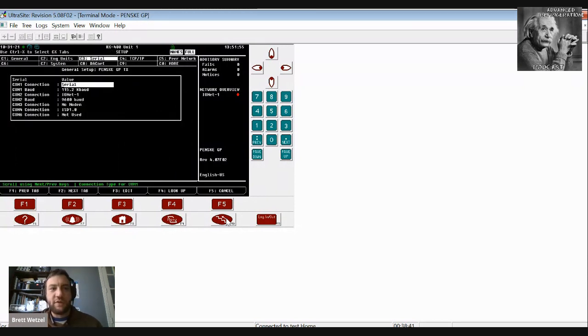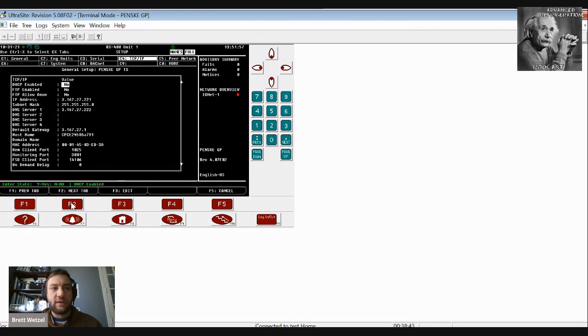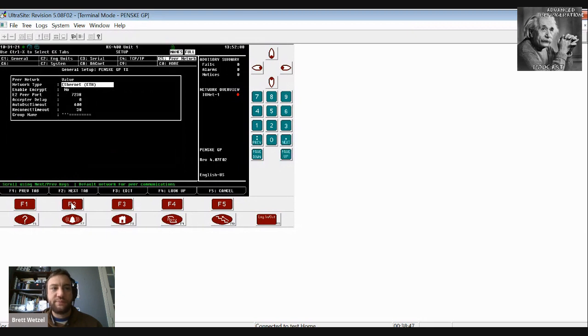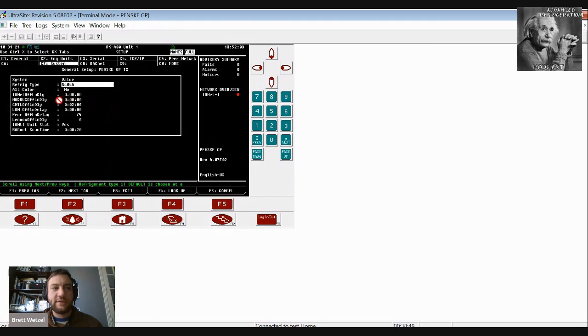This gives you all the communication information. There's the IP addresses, delays for the networks. So if you have a controller that's losing communication every once in a while, usually I see standard has a 2-minute delay in here. IONet delay is the CPC boards. Modbus would be your 678, 679 controllers. CMTL is actually Comtrol. LAN delay is Echelon. And if this controller did have the capability to talk to Novar boards, you'd see an NVR delay on here.